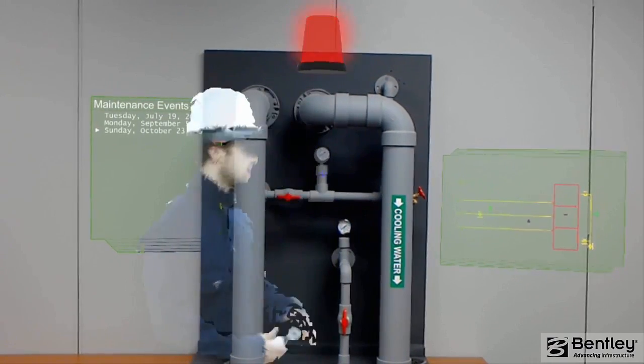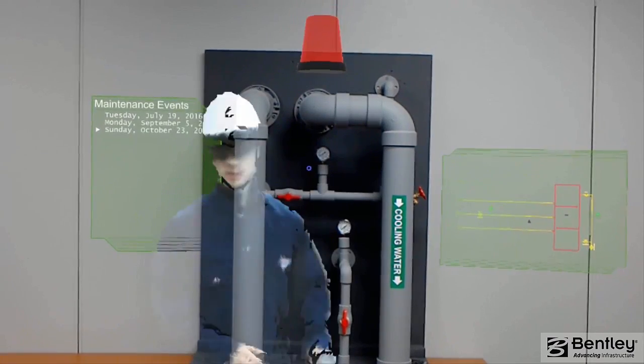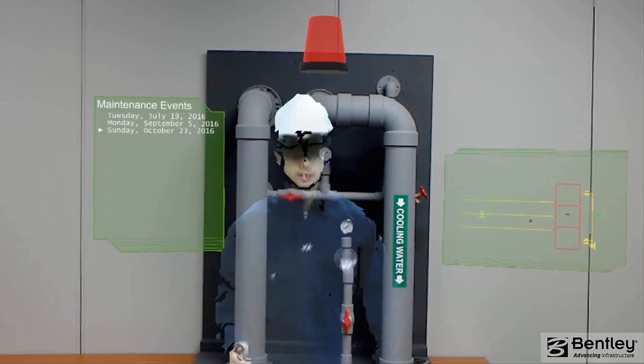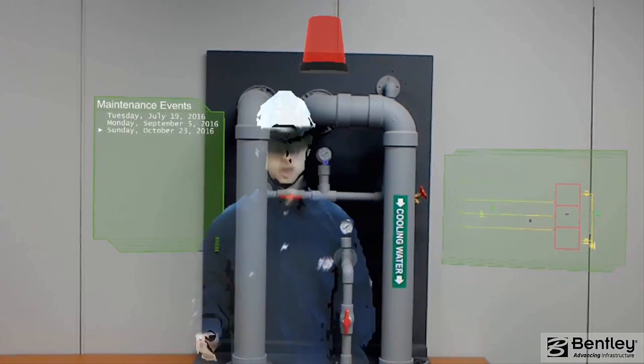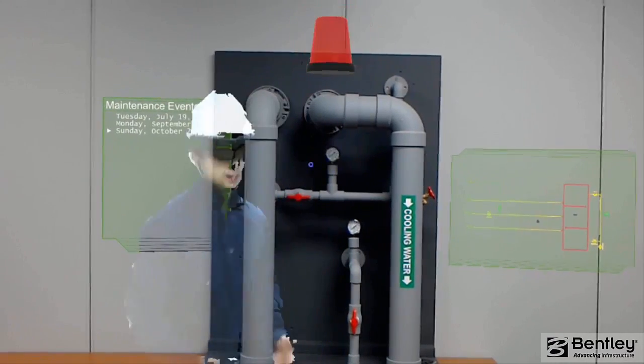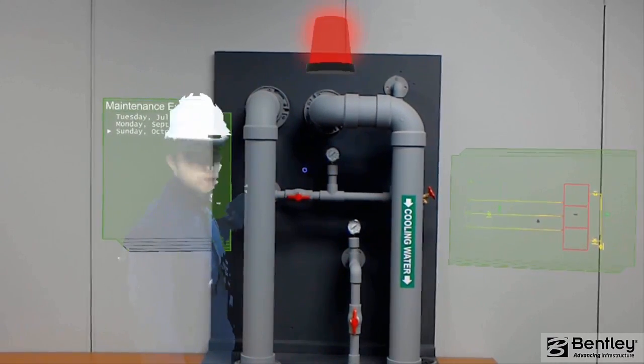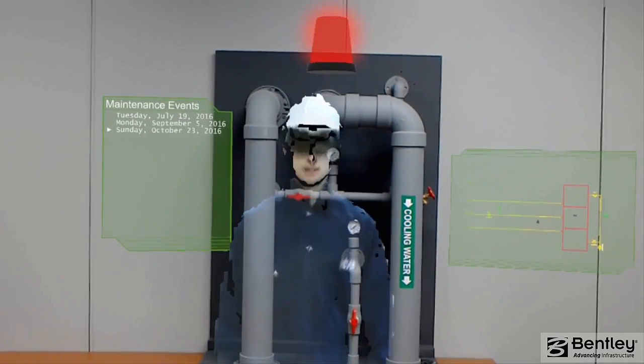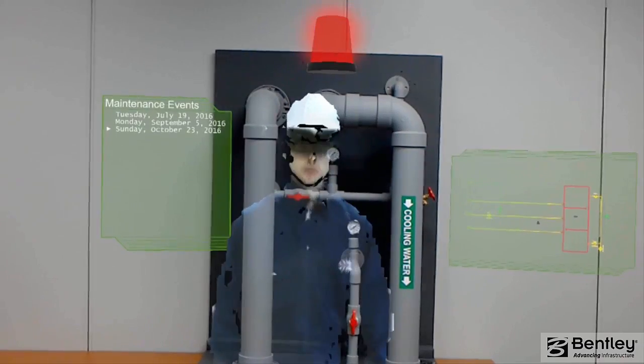Measured pressure was way too low, so I replaced it. But we did the same thing last month and back in July. So that means we replaced it three times in four months. That's way too much for this type of device because they usually last more than a year. It indicates there's probably something wrong with the system, but we would need further investigation to confirm that. See my report for additional details.